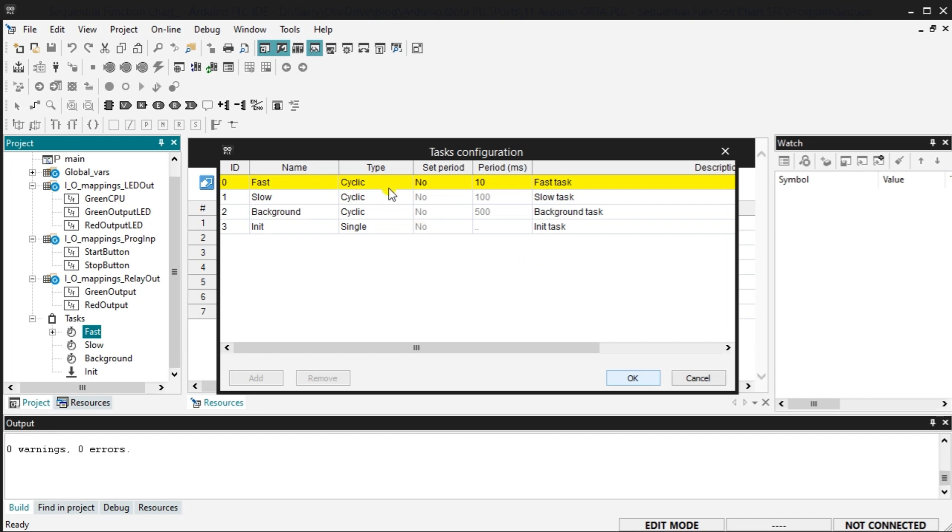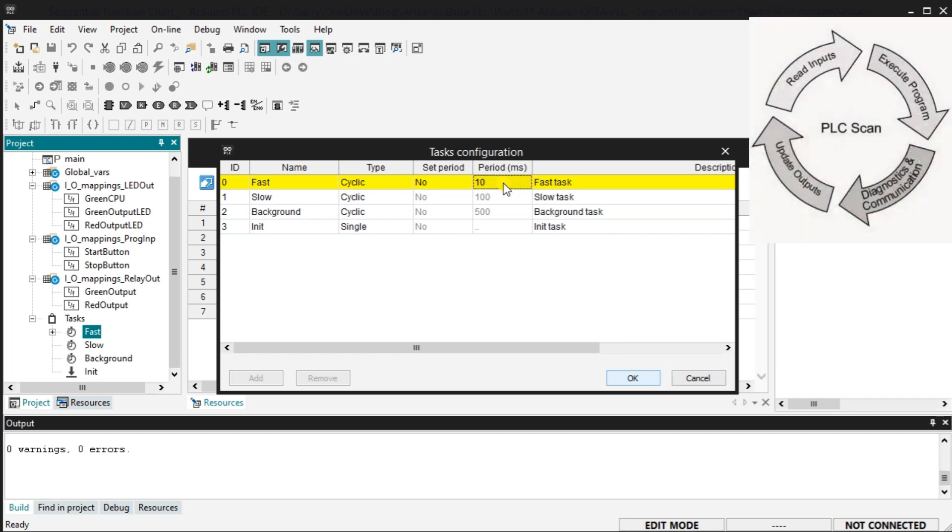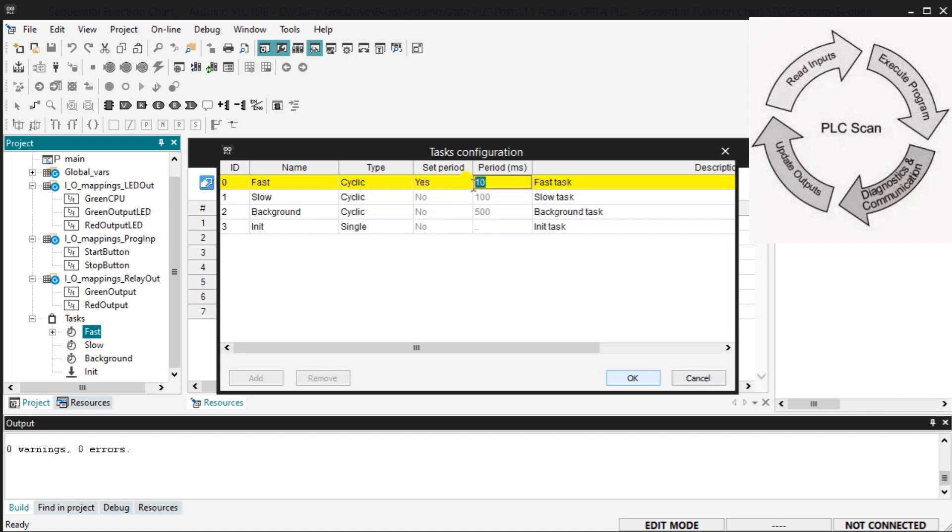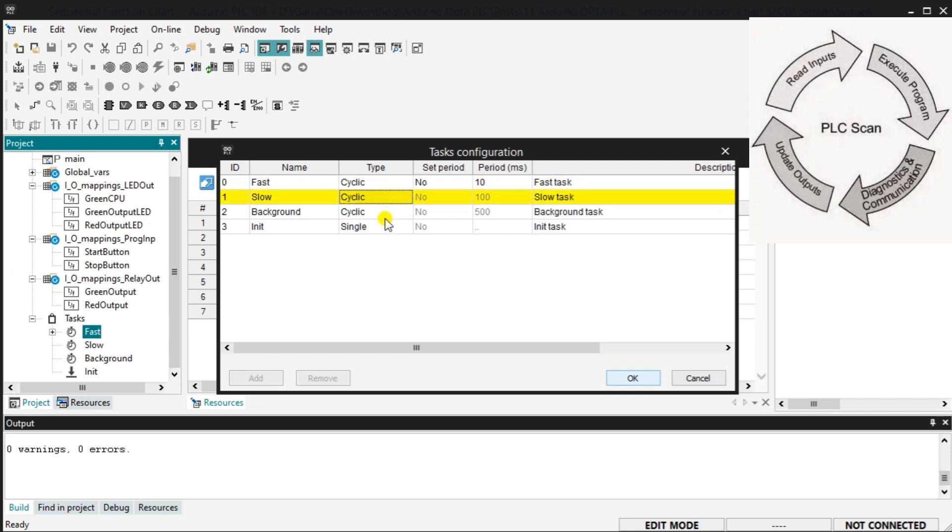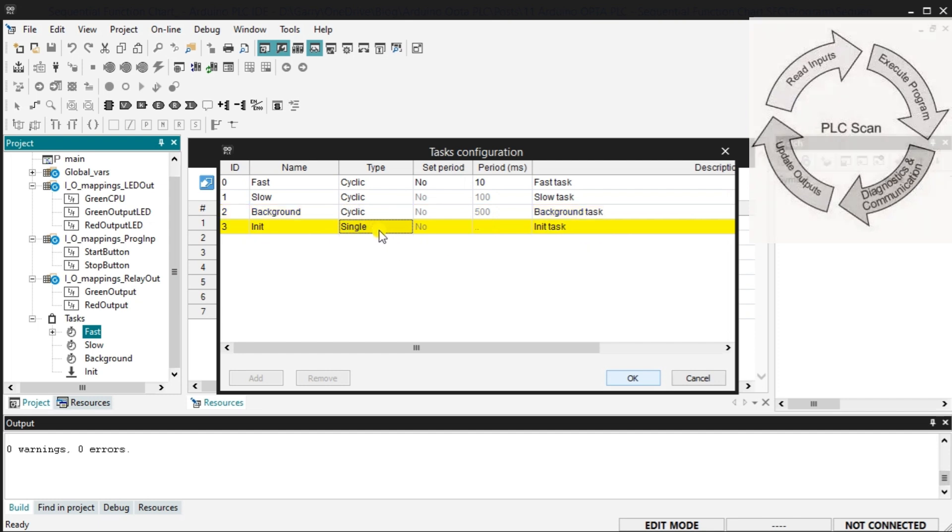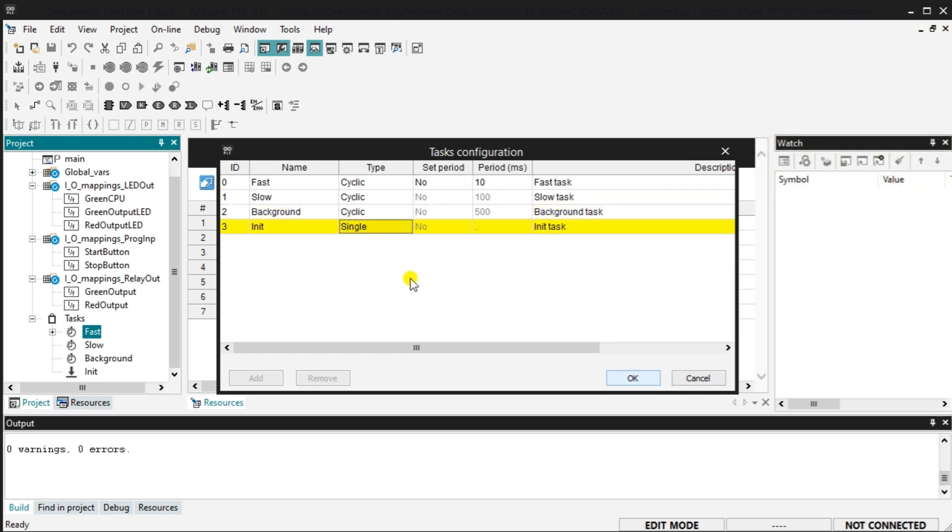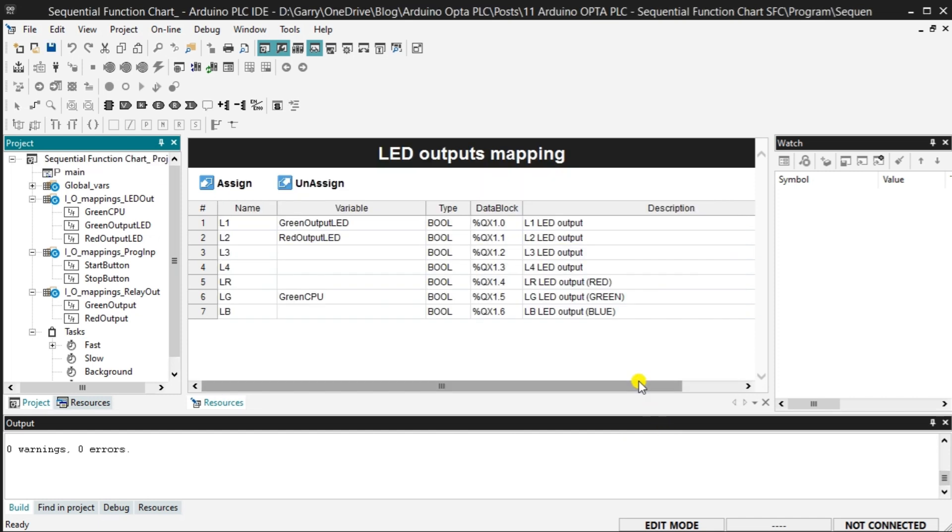The fast task folder will execute your program cyclically every 10 milliseconds, 100 times per second. This can be changed by changing the set period to yes. You can then enter a value in the period column in milliseconds. The majority of programs will be placed in this folder. The slow and background task folders will also scan cyclically. They are both set at a fixed period of 100 and 500 milliseconds, 10 times per second and 2 times per second. The init or initialize task folder sets variables or conditions in the PLC after it powers up. It will run for a single scan. Select OK to close the task configuration window.